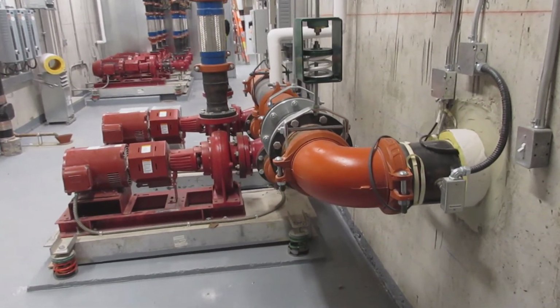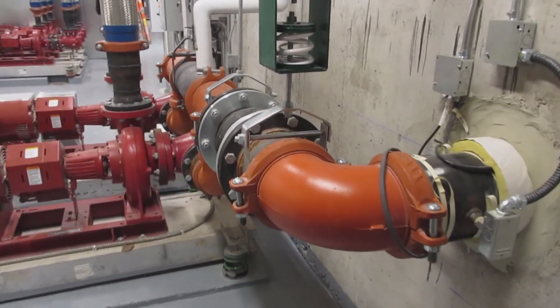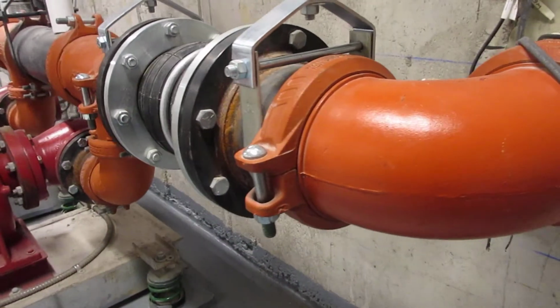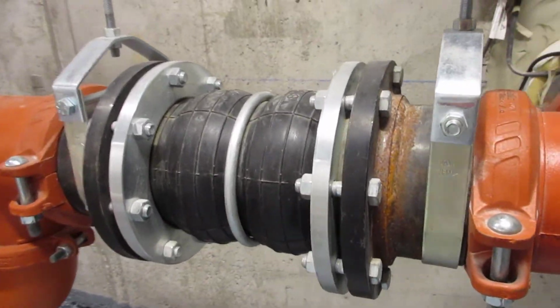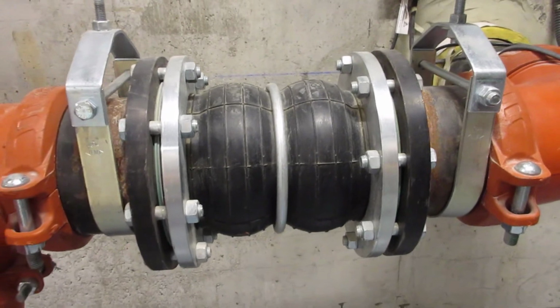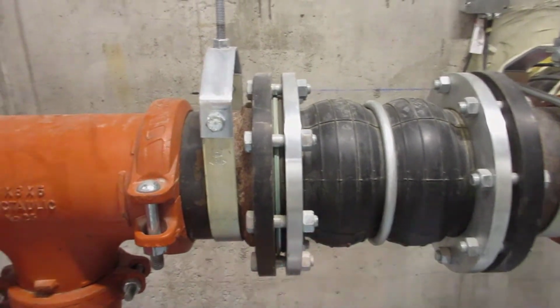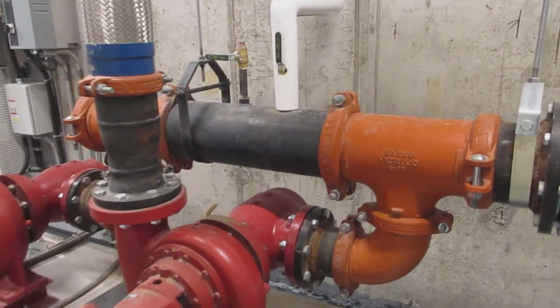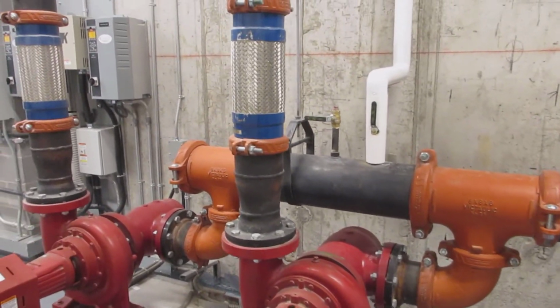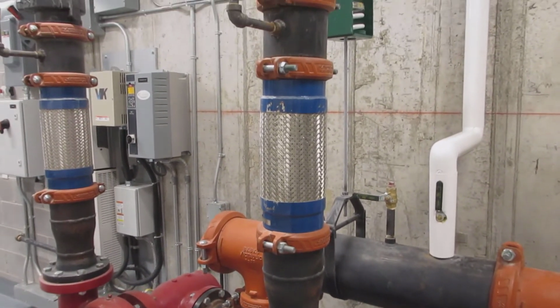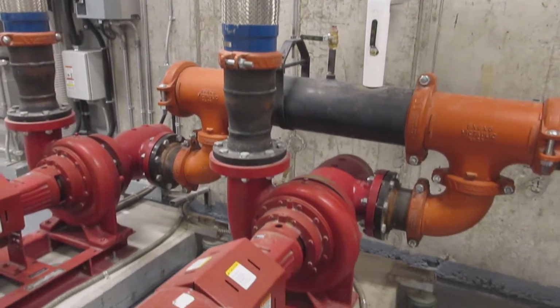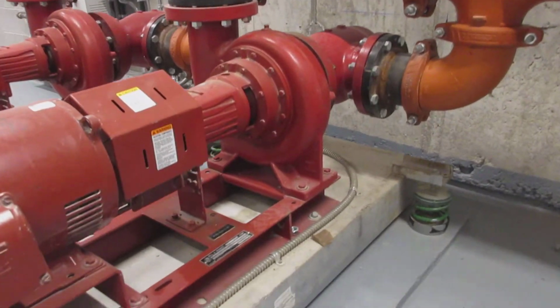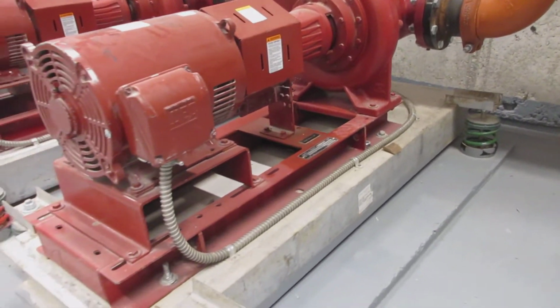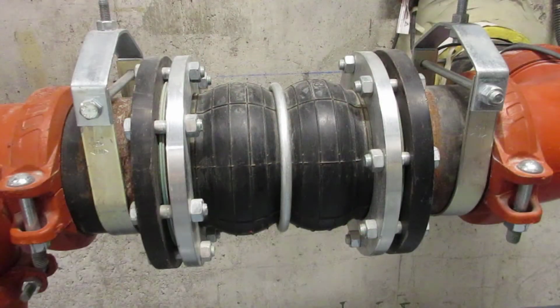This is the suction pipe bringing water from the cooling tower. It is supported with vibration isolators and includes a double sphere neoprene flanged expansion joint or flex connector. The two end suction base mounted pumps each have their own flexible braided metal connector on the discharge side, which we discuss in a separate training video. The pumps are secured to concrete inertia bases supported by 2-inch deflection floor springs, which are also discussed in a separate training video.